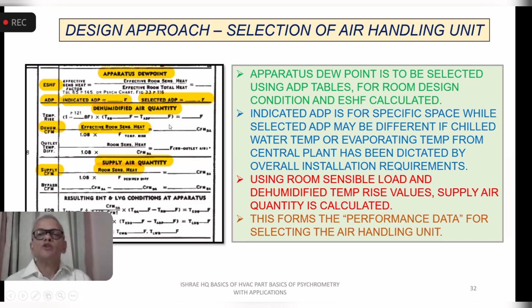Apparatus dew point is to be selected using the ADP table for the room design condition and the calculated ESHF, effective sensible heat factor. Indicated ADP is for a specific space, while selected ADP may be different if a chilled water system is used. If you have a common system supplying chilled water to various air handling units, it's not necessary that all the spaces have the same ADP, because it is dictated by the room design temperature and the space sensible heat factor. Then you have to use the selected ADP based on the chilled water. Indicated ADP could be different.